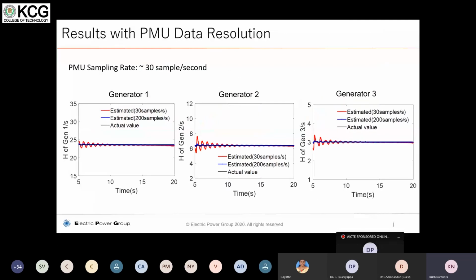With the previous data, what we calculated was at a very high sample rate of 200 samples per second. We reduced it to what a practical PMU measures today, and we still have very good results. You can see that for the 3 respective generators, based on their own MVA rating. So this is using the PMU data with the same 30 samples per second.